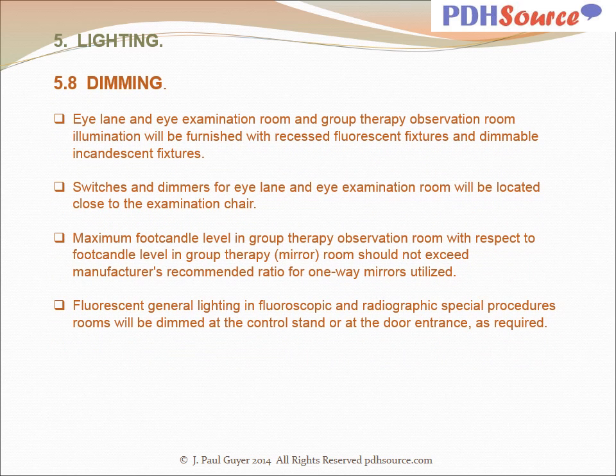Eye lane and eye examination room and group therapy observation room illumination will be furnished with recessed fluorescent fixtures and dimmable incandescent fixtures. Switches and dimmers for eye lane and eye examination room will be located close to the examination chair. Maximum foot candle level in group therapy observation room with respect to foot candle level in group therapy mirror room should not exceed manufacturer's recommended ratio for one-way mirrors utilized. Fluorescent general lighting in fluoroscopic and radiographic special procedures rooms will be dimmed at the control stand or at the door entrance as required.